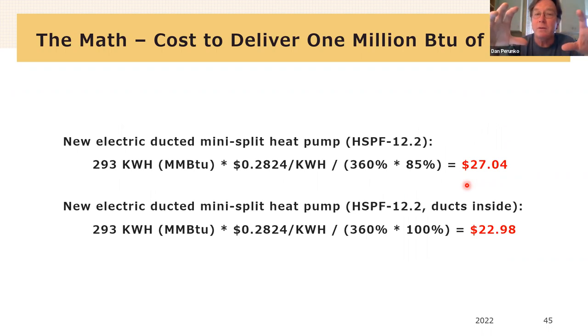If we go to heat pumps, we can do the same thing, right? There are two different efficiency numbers represented in here. HSPF, heating seasonal performance factor, of 12 is a rating, and it has a COP, which is coefficient of performance. The COP is basically how many times better than electric resistance this would be. And this has a COP of 3.6. And heat pumps range from about 1.5 to 5 in terms of how many times better than electric resistance they are, depending on conditions, right?